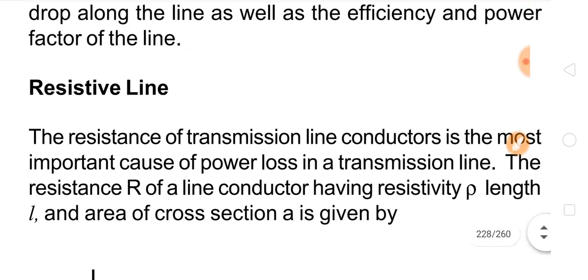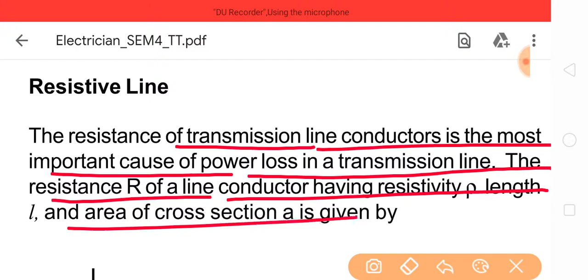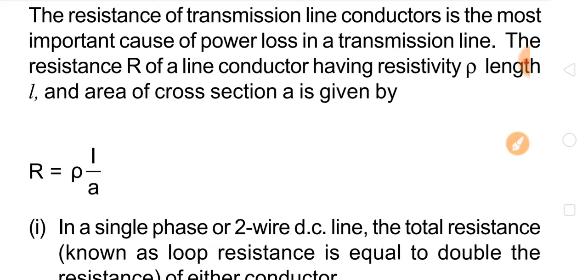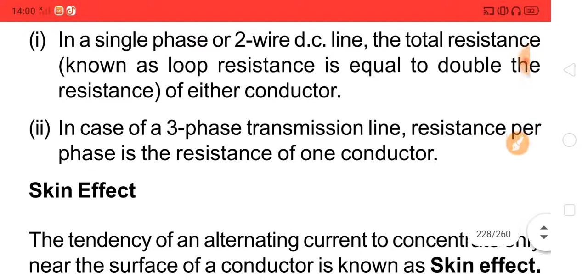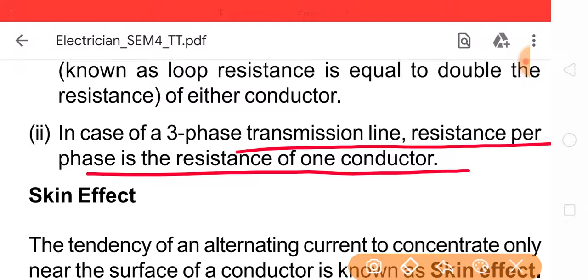The resistance R of a line conductor having resistivity rho, length L and cross-sectional area A is given by R = rho L / A. In a single phase 2 wire DC line, the total resistance, known as the loop resistance, is equal to double the resistance of one conductor. In case of a 3-phase transmission line, the resistance per phase is the resistance of one conductor.